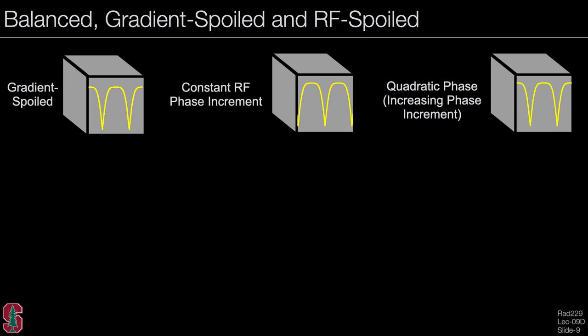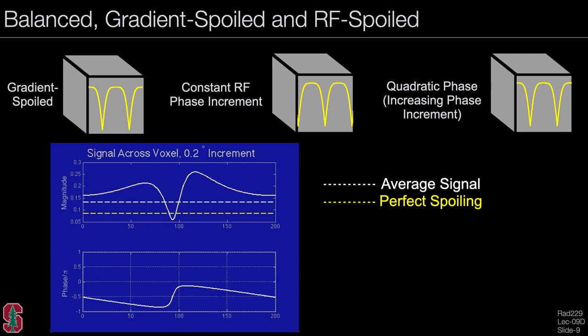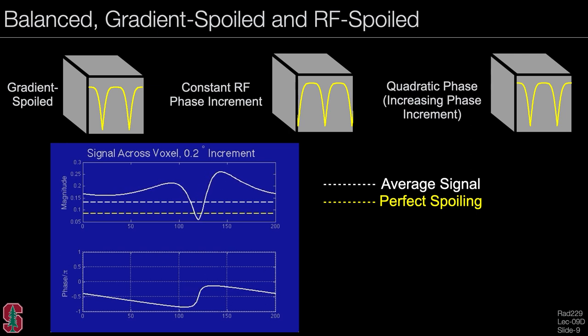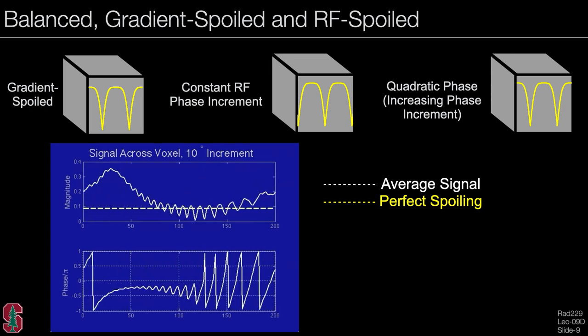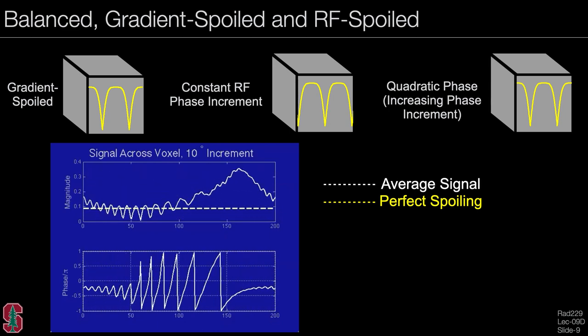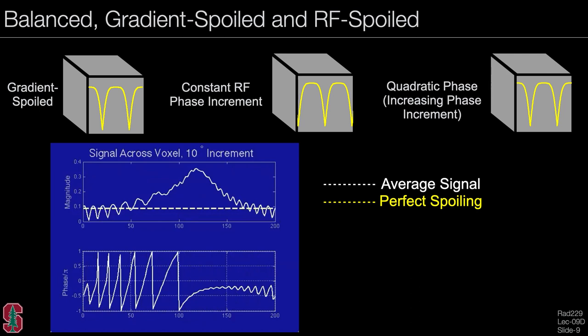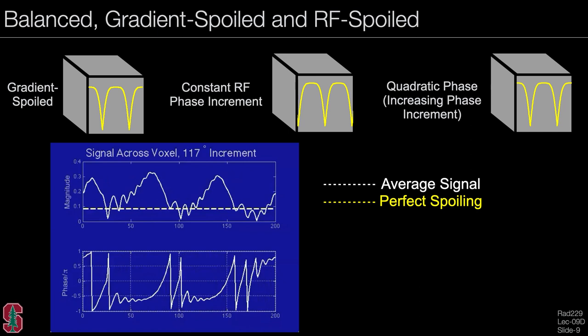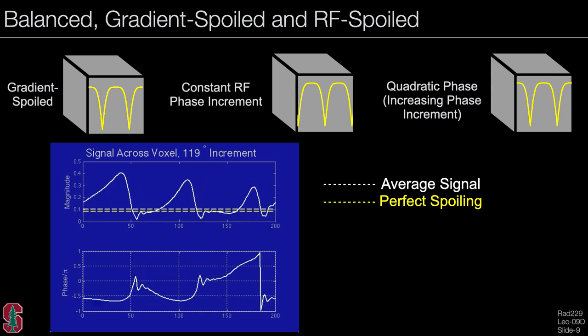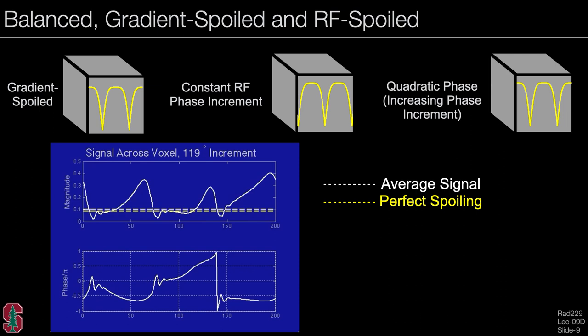With a very small phase increment, the profile resembles a balanced SSFP profile but with some asymmetry due to shifting. A larger phase increment moves the signal much more quickly. At 117 degrees, a typical value used, you really cannot track what is happening, but the dashed line shows that the overall average signal matches the case of perfect spoiling. Going slightly off this value, the average signal no longer matches perfect spoiling, so the choice of increment is really important.